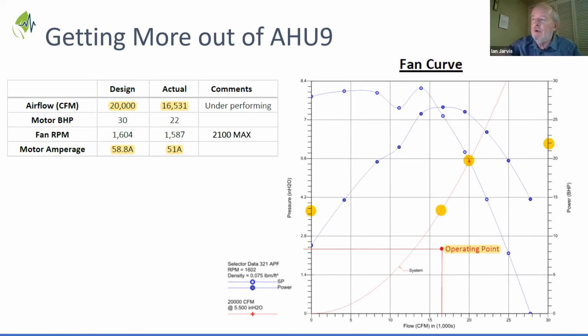So the operating point you see there should be on the curve, and it's not. It could have to do with air leakage. So Matt, not sure where your guys would have tested the airflow, but if it's downstream of the unit, perhaps we're losing air from flexible connectors or holes in the ductwork from previous testing work that's been done.